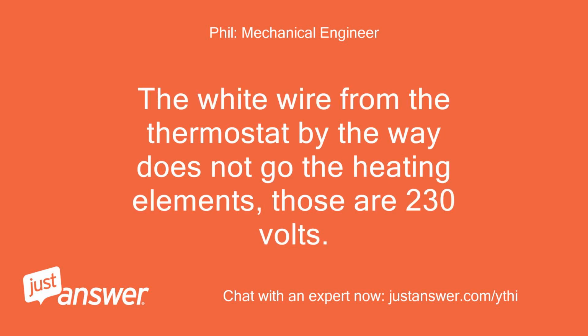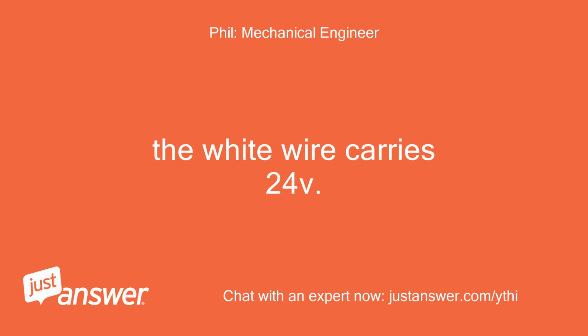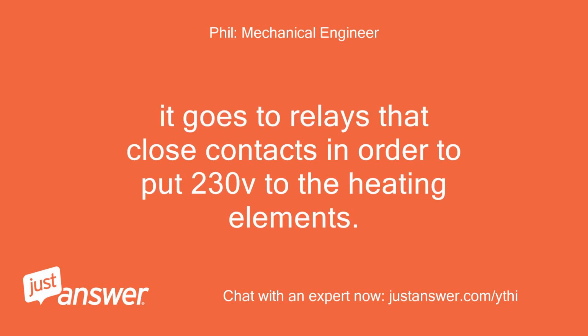The white wire from the thermostat, by the way, does not go to the heating elements. Those are 230 volts. The white wire carries 24V. It goes to relays that close contacts in order to put 230V to the heating elements.